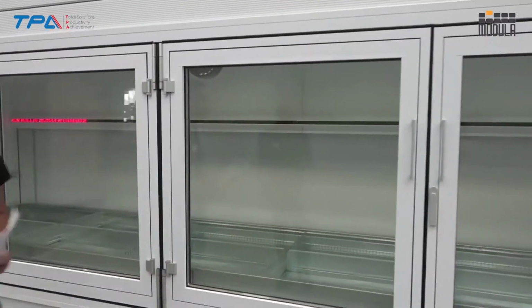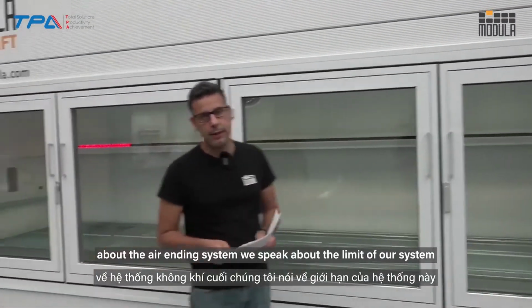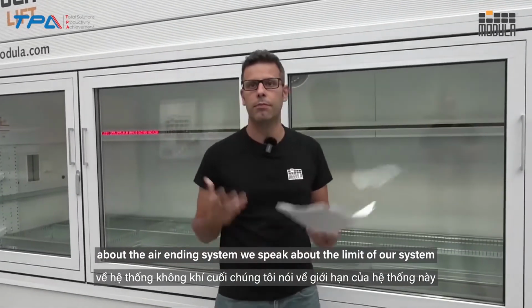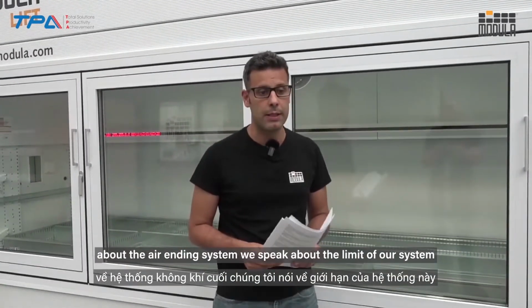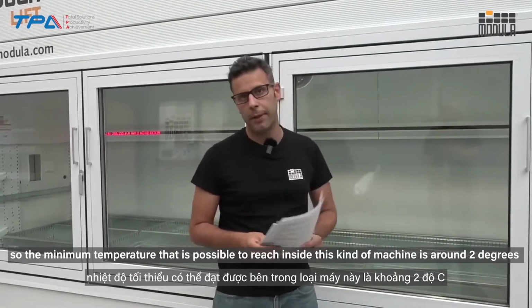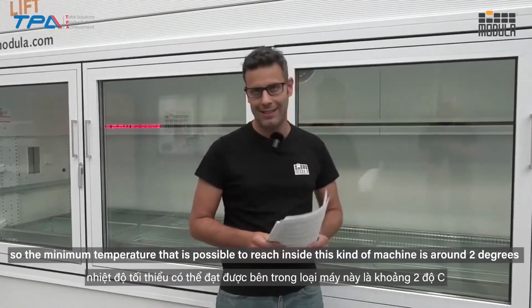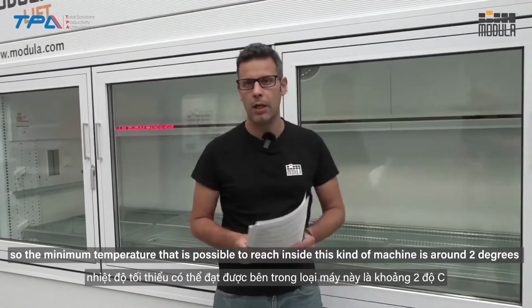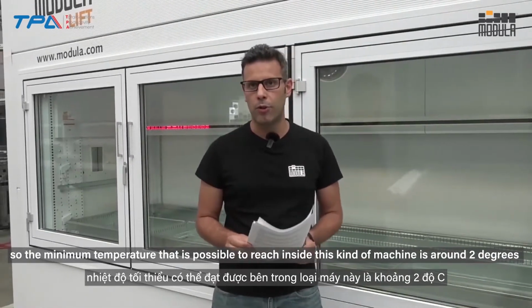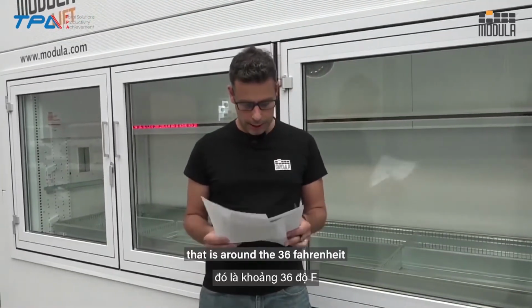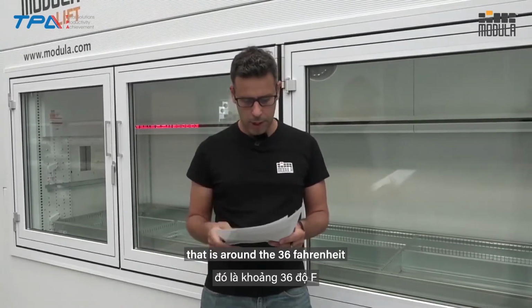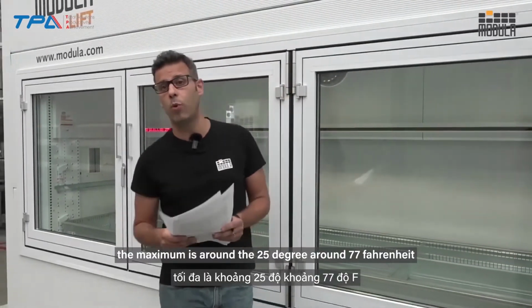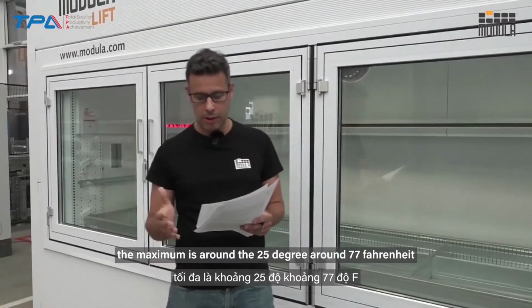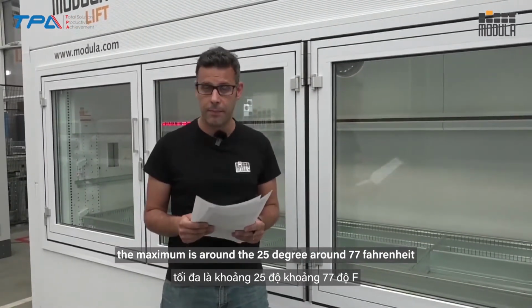Okay, about the air handling system, we speak about the limits of our system. The minimum temperature that is possible to reach inside this kind of machine is around 2 degrees, that is around 36 Fahrenheit. The maximum is around 25 degrees, around 77 Fahrenheit.